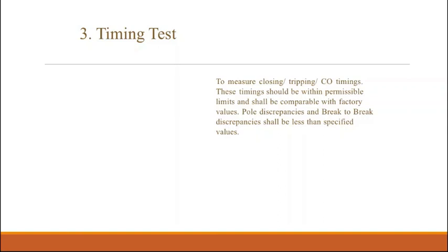So what will happen, even though the relay sends the fault command immediately after the time delay we set in the protection relay, once it gives the command, we expect the breaker to trip as soon as possible, but it will take its own time. So to determine this time, we can calculate the fault clearance time offered by that particular circuit. Also for coordination purposes, this timing test is most important.